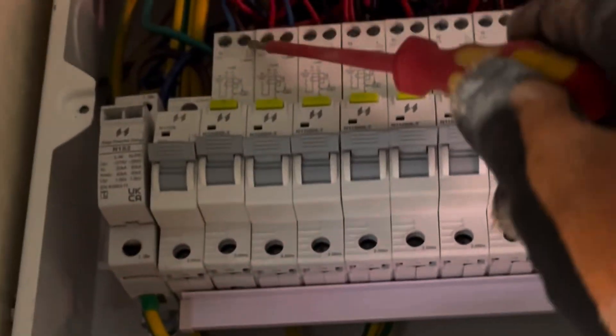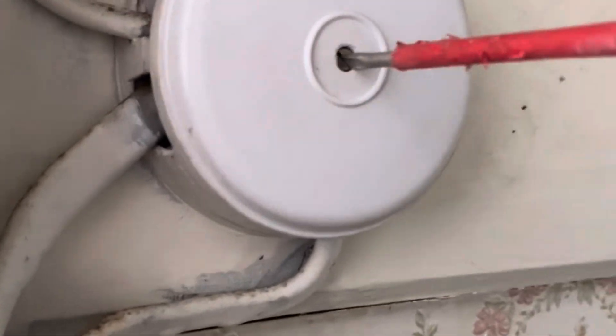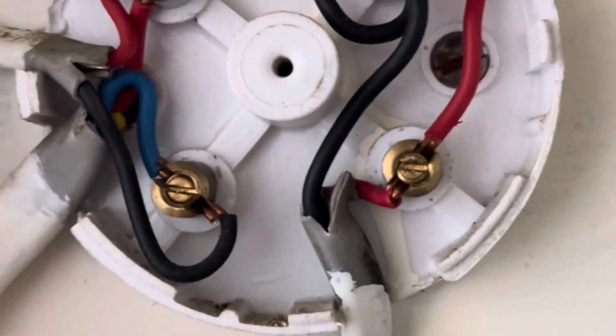If you're like me and you think why didn't these lighting circuits trip the RCD - these RCDs work but why didn't they trip? Look at the state of it. It's interesting to see what can get away with an RCD. I found out exactly why the RCD is not tripping - it's got joint boxes everywhere: joint, joint, joint, joint. And when you don't bother connecting the earth of course the RCD is not going to work. That is why we're rewiring the whole house.